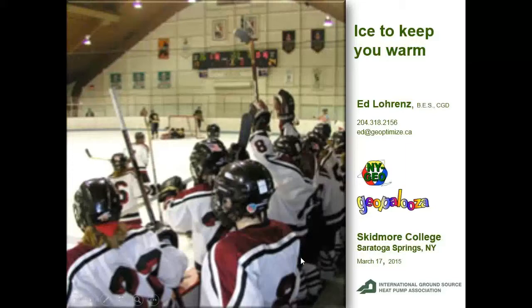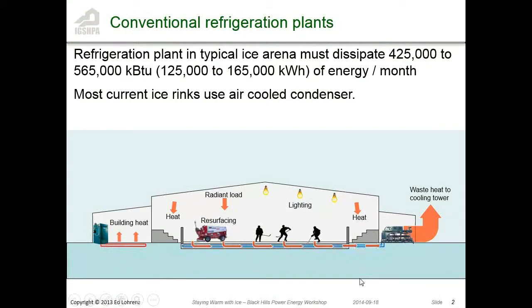Typical ice rink. You're sucking heat out of here, you're dumping it out here, you're adding heat from lighting and whatever else, and the building heating system. Very energy intensive buildings. A typical ice rink has to get rid of about 425 to 565,000 BTUs of energy per month, or kBtus per month. Most ice rinks have a cooling tower sitting on them and they're just dissipating that energy straight to the atmosphere, just to get rid of it.